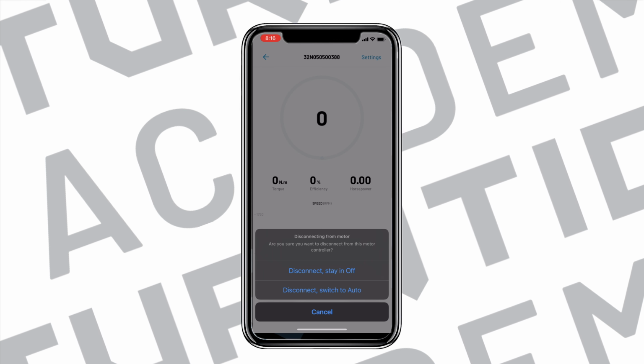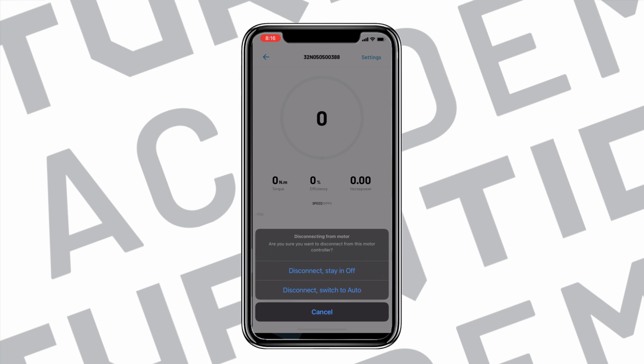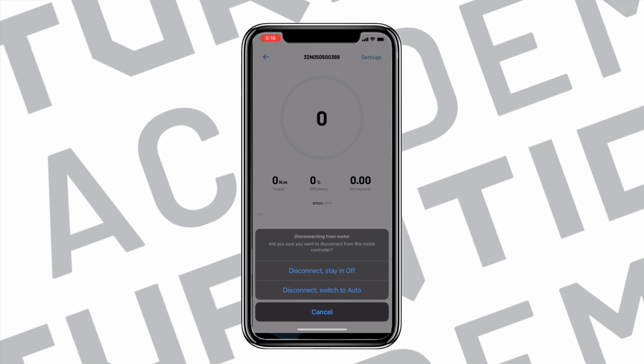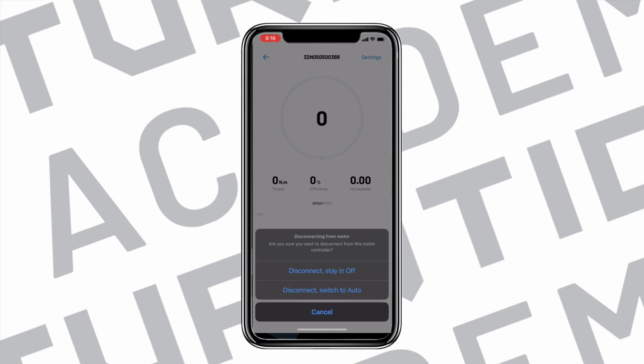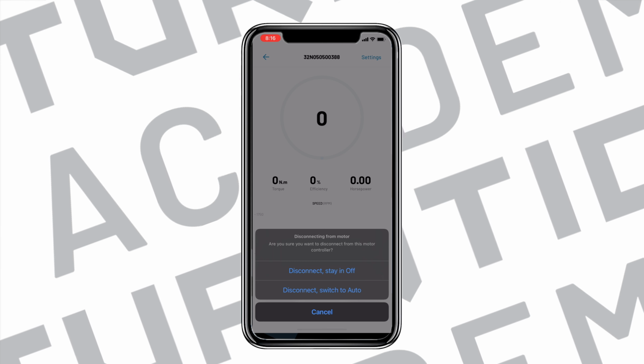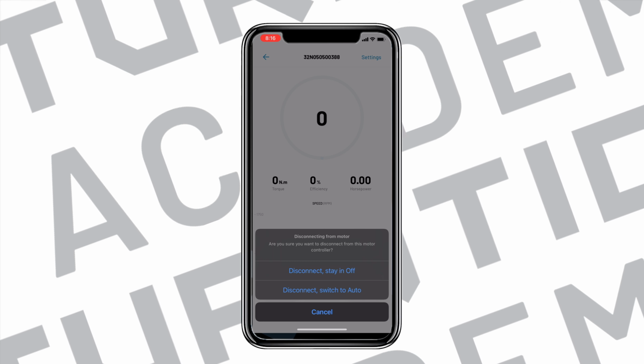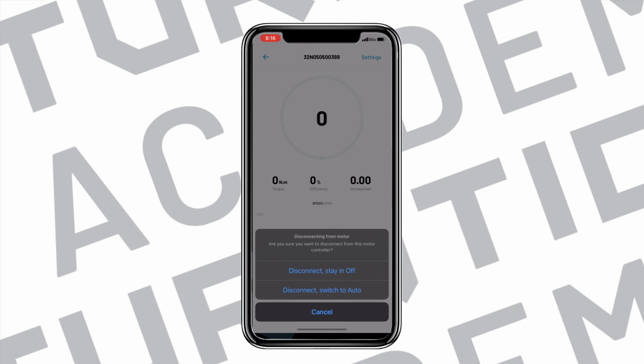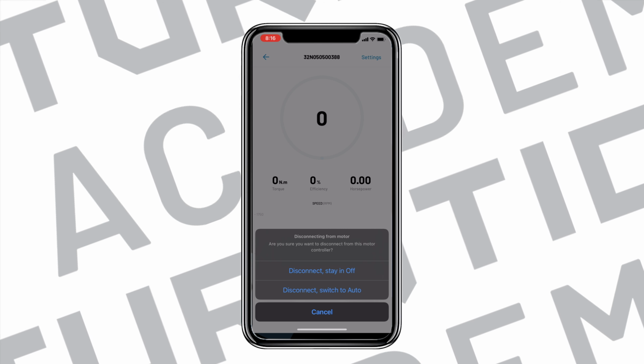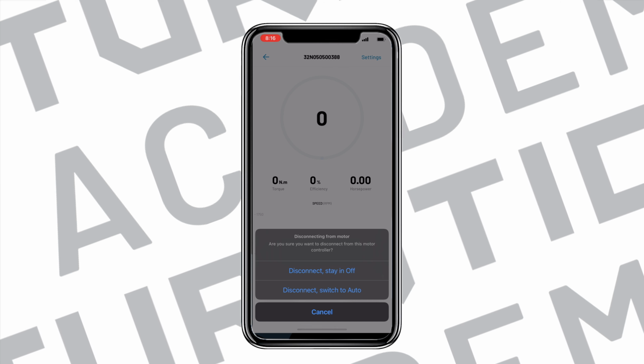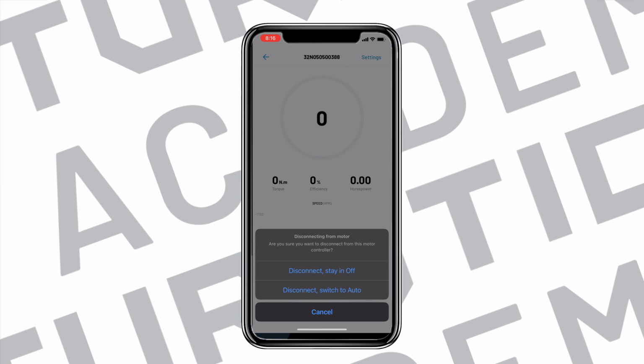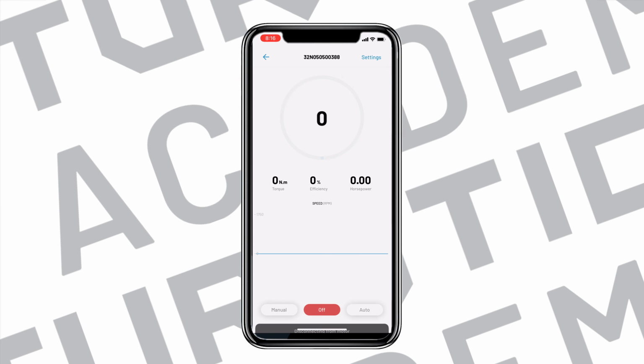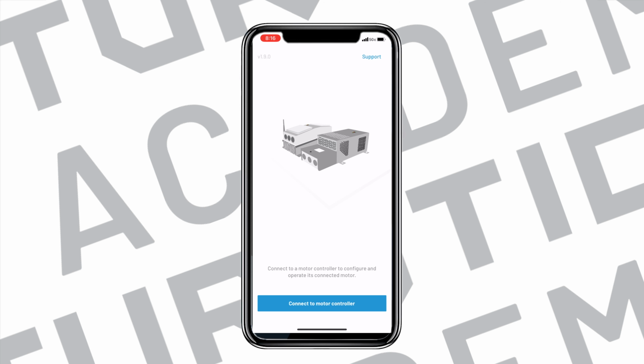Here too, if exiting the app while in off mode, a prompt appears asking the technician if they wish to remain in off or return to auto mode. The final option is auto. In this mode, the RTU and Turntide motor system operate normally. The system must be left in auto. Finally, disconnect from the motor controller by touching the back arrow in the upper left and confirm the choice.